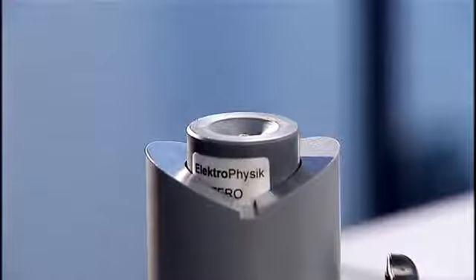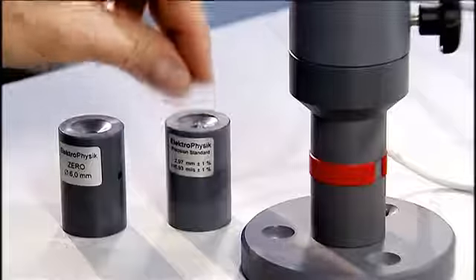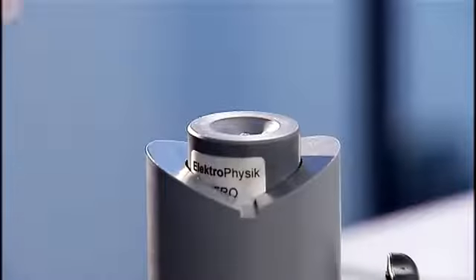For the zero calibration, a zero standard supplied with the gauge and the matching steel balls are used. The steel ball is put into the calibration cap. Together with the steel ball, the calibration cap is then put onto the sensor to take a reference reading.